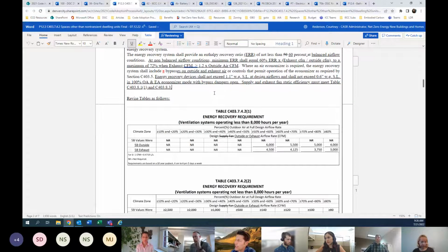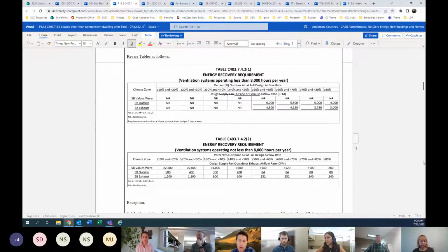And then the last thing is, I think on the tables, we lowered the values for two reasons. One was in the last round, it was kind of, to push in under 8,000 hours, there was no requirement for energy recovery. So, to put it back in the code. And then we did some more analysis, and when you look at packaged units, it's actually a lot less expensive. So we pushed the energy recovery down. It's one of the best ways to get energy efficiency in a building.